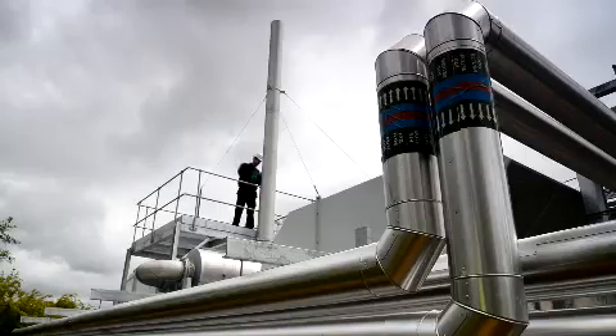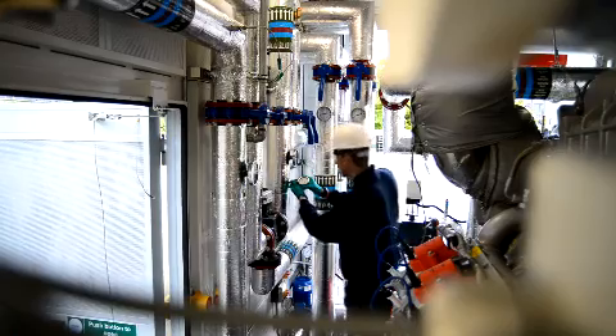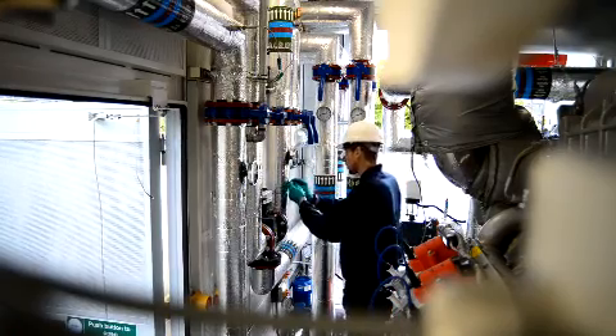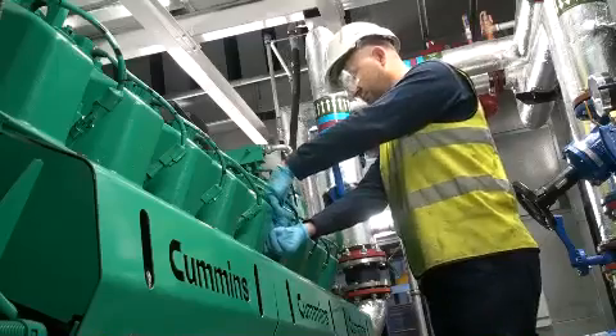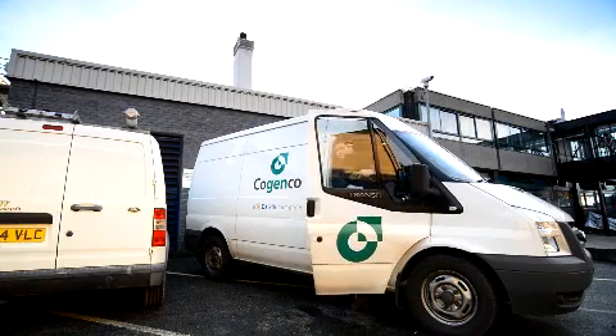Within that 15-year period, we're not only doing the routine servicing, which incorporates oil changes, spark plugs and filters, typically what you'd expect on a spark ignition engine, but we're also doing major overhauls. One of the key requirements of a CHP scheme is to ensure you've got long-term operational contracts in place, ideally with the CHP provider who installed it, so you maximise the potential benefits from the unit over that period.